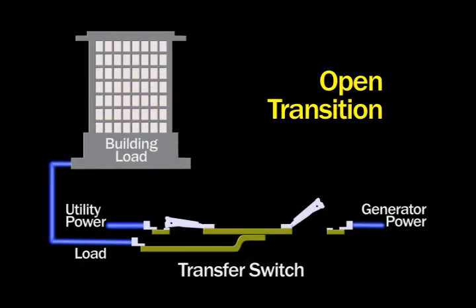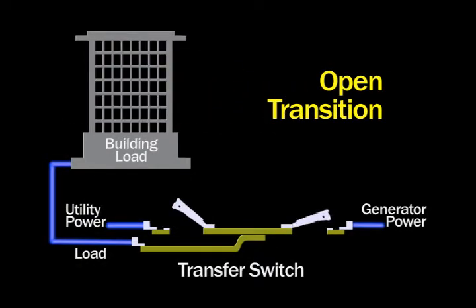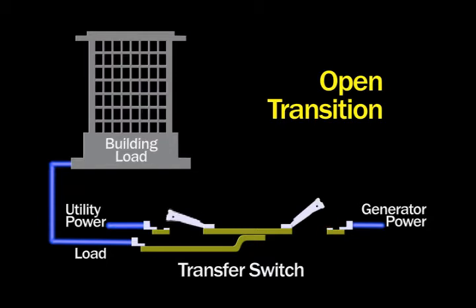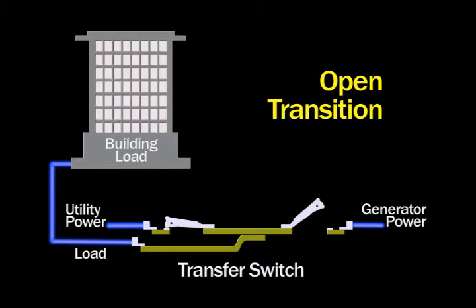The automatic transfer switch must safely make the transition of power from one source to the other. Open transition mode isolates one power source before connecting to the alternate source. This is also referred to as break-before-make switching.